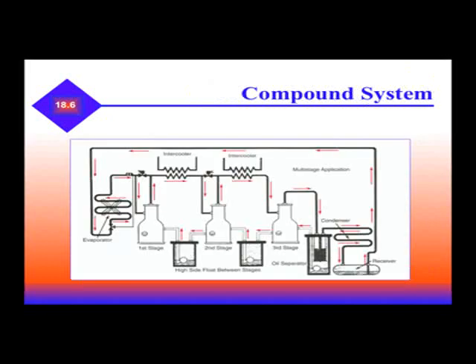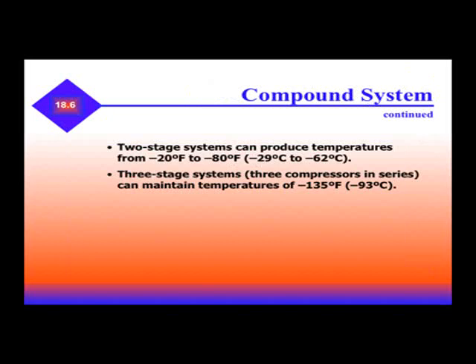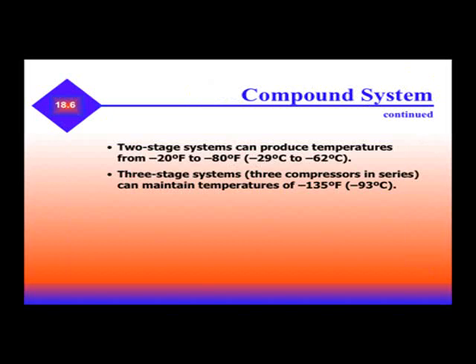This is an example of a compound system. The difference between the compound and the cascade is that in the cascade, we can use two different refrigerants, while in a compound system we can only use a single refrigerant. Two-stage systems can produce temperatures from negative 20 to negative 80 degrees, and three-stage systems can go down to negative 135 degrees.